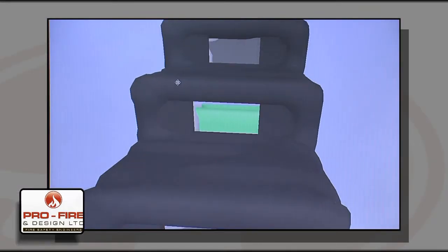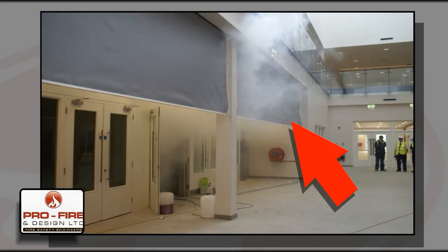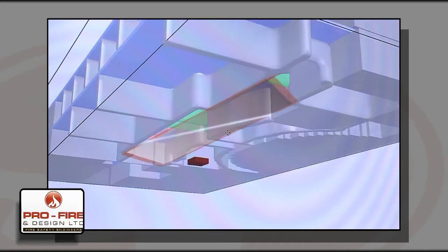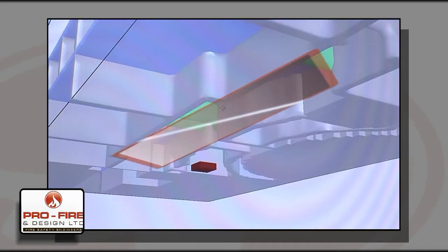The strategy involved the use of roof-level smoke ventilators and smoke curtains that drop to a predetermined height around the edge of the voids. This ensures smoke from a fire discharging into the mall does not impede the escape routes for occupants.